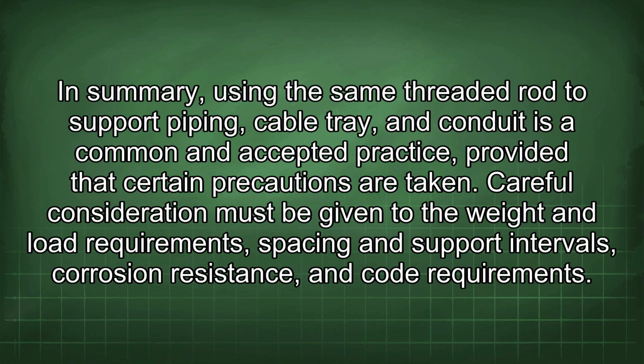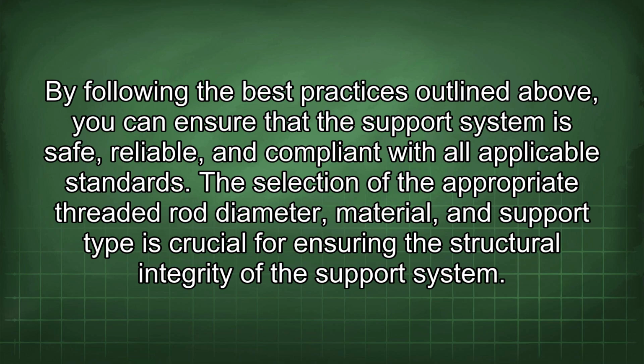In summary, using the same threaded rod to support piping, cable tray, and conduit is a common and accepted practice, provided that certain precautions are taken. Careful consideration must be given to the weight and load requirements, spacing and support intervals, corrosion resistance, and code requirements. By following the best practices outlined above, you can ensure that the support system is safe, reliable, and compliant with all applicable standards. The selection of the appropriate threaded rod diameter, material, and support type is crucial for ensuring the structural integrity of the support system.